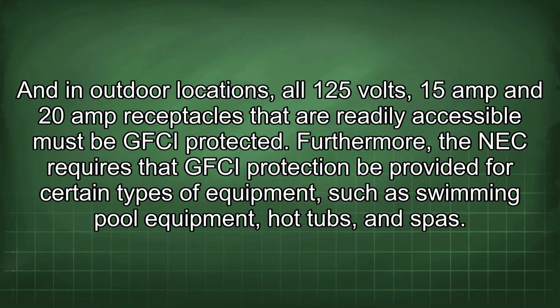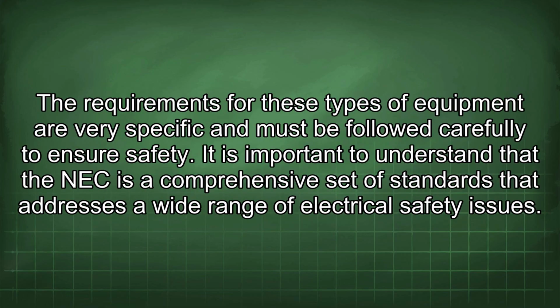And in outdoor locations, all 125 volt, 15 amp and 20 amp receptacles that are readily accessible must be GFCI protected. Furthermore, the NEC requires that GFCI protection be provided for certain types of equipment, such as swimming pool equipment, hot tubs, and spas. The requirements for these types of equipment are very specific and must be followed carefully to ensure safety.